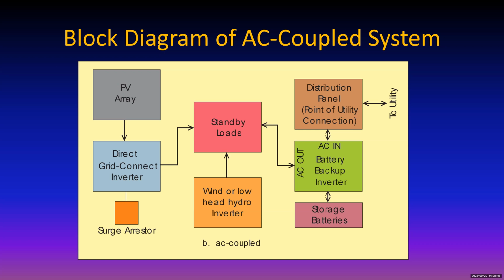So that AC out is kind of misleading because you can put AC into there too, and not everybody realized that long ago. But anyway, that is the principle. There is a bus bar in there. And again, that power first goes to storage batteries to keep them charged. Once the batteries are happy and the standby loads are happy, any excess goes to the utility. Of course, with this one, when the utility goes down, there's an interesting situation, and even with the DC coupled, and here's a question, we'll get to that in just a second, hold on.